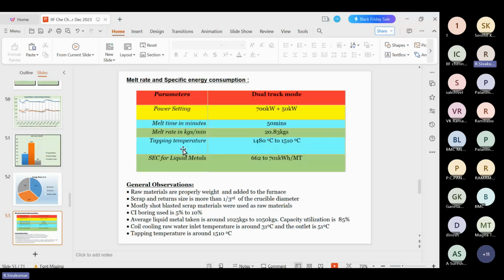The same company is installing a 750 kilowatt dual track furnace, and the furnace melting capacity is 1,000 kgs. The power setting was almost 700 kilowatt plus 50 kilowatt, and the melting time is 50 minutes. The melt rate is 20.83 kgs per minute, and the tapping temperature ranges between 1480 and 1510 degrees. The specific energy consumption for liquid metal varies from 662 to 701 kWh per metric ton.